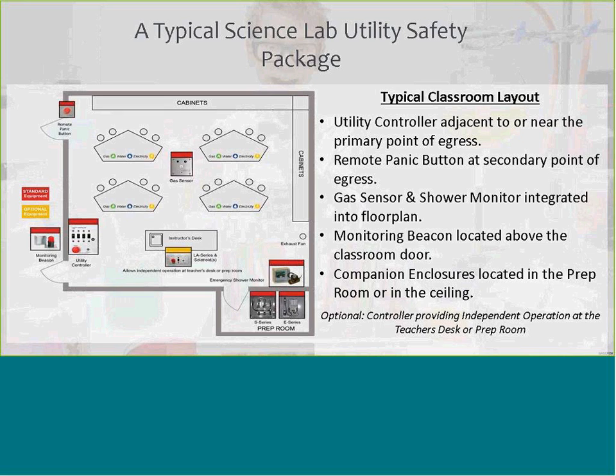You do not want to have the flow sensor shut any of the water off. The water that goes to the emergency shower is always before your system that's going to be designed to take care of the water in that classroom. It has to be free of any obstructions there.